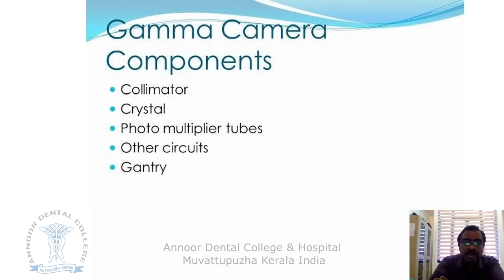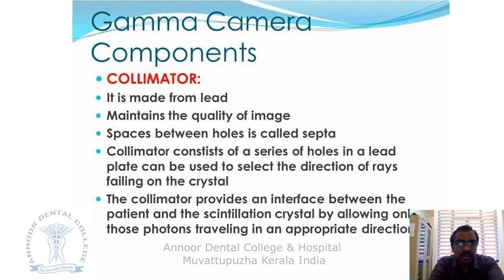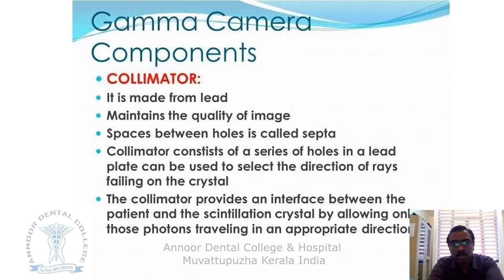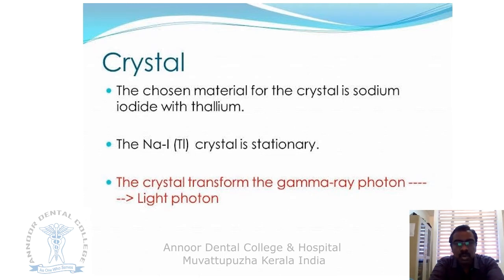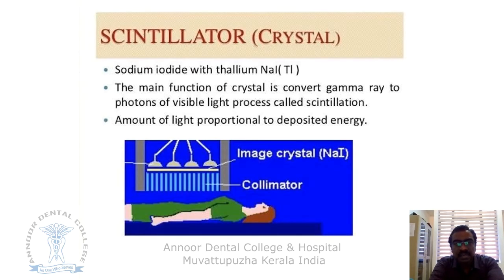The gamma camera has several components: a collimator, crystals, photomultiplier tubes, other circuits, and a gantry. The collimator is made of lead and maintains image quality. The spaces between the holes are called septa. The collimator consists of a series of holes in a lead plate used to select the direction of gamma rays falling on the crystals, providing an interface between the patient and the scintillation crystals. The chosen crystal is sodium iodide with thallium. It is stationary and transforms gamma ray photons to light. The crystal — the scintillator — converts gamma rays to visible light photons, with the amount of light proportional to the energy deposited.